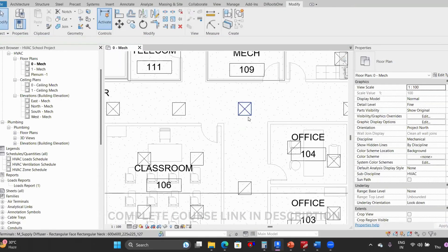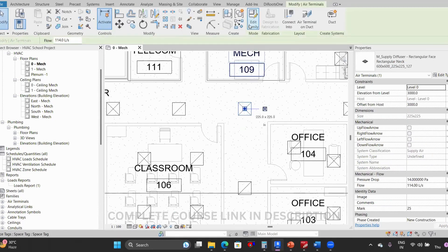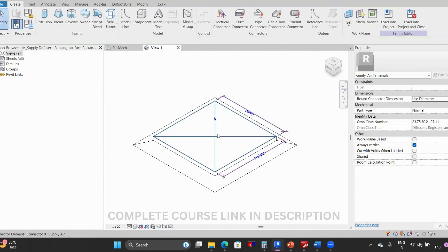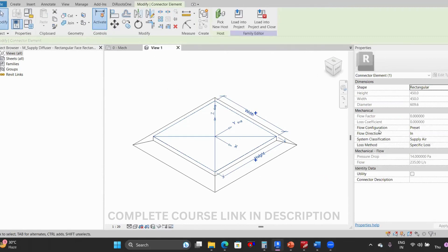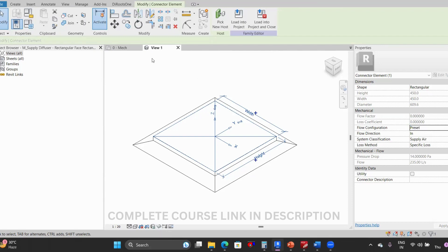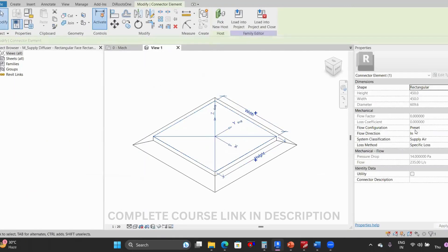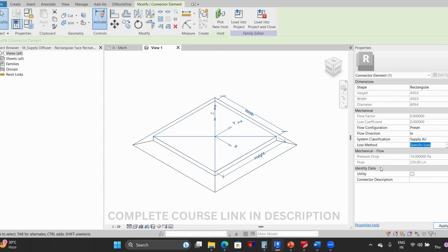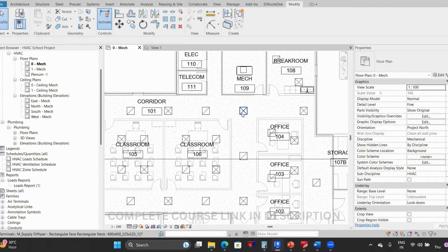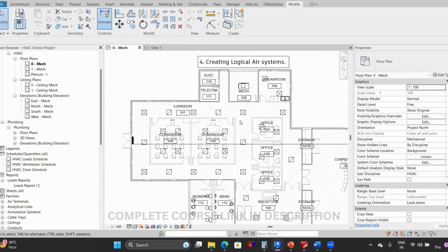Now let's look at a diffuser as the target. Go to edit family and select the connector. Here the flow configuration should be 'preset' because we are manually entering the flow information. The flow direction should be 'in' because air is going into the diffuser. System classification is supply air — same as the source. Make sure these settings are correct before you create the system.